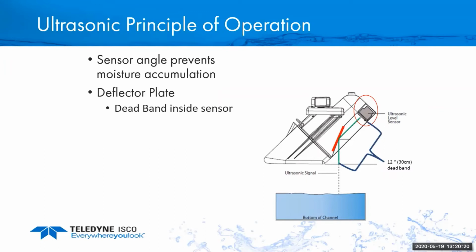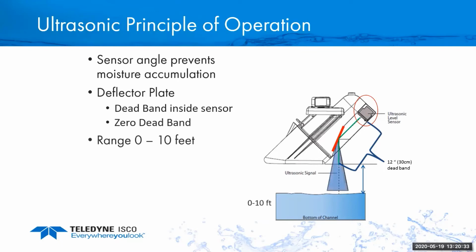That means the water will go all the way up to the bottom of the laser before it will not read levels. So that 12-inch deadband is now accounted for in the sensor design itself. So virtually zero deadband ultrasonic on this design. It can be 10 feet away from the water. So it can be, again, a long ways away from the water.